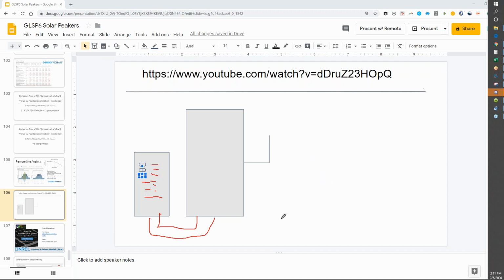Utility lines either come in from the ground or they come in from overhead. And a solar array on top of the rooftop, if here's the roof and your conduits are coming down into this disconnect switch, it's very tempting to bring that in through the top of the switch because that's where the solar array is. And it can also get confusing because the solar array is a source of power supply, and you may be doing it on a supply side connection.